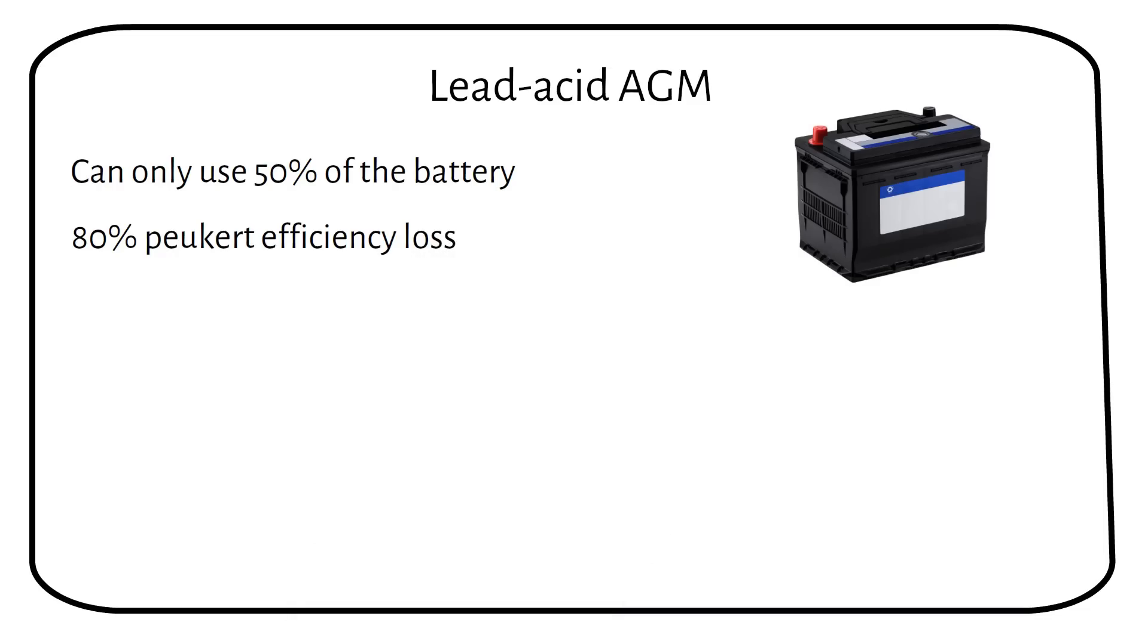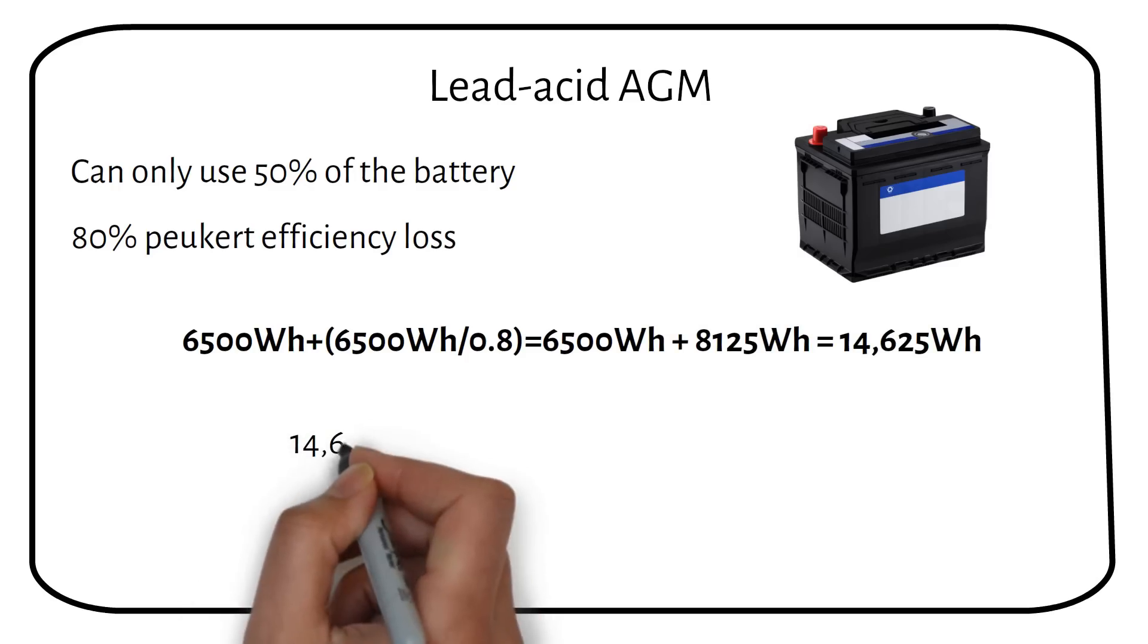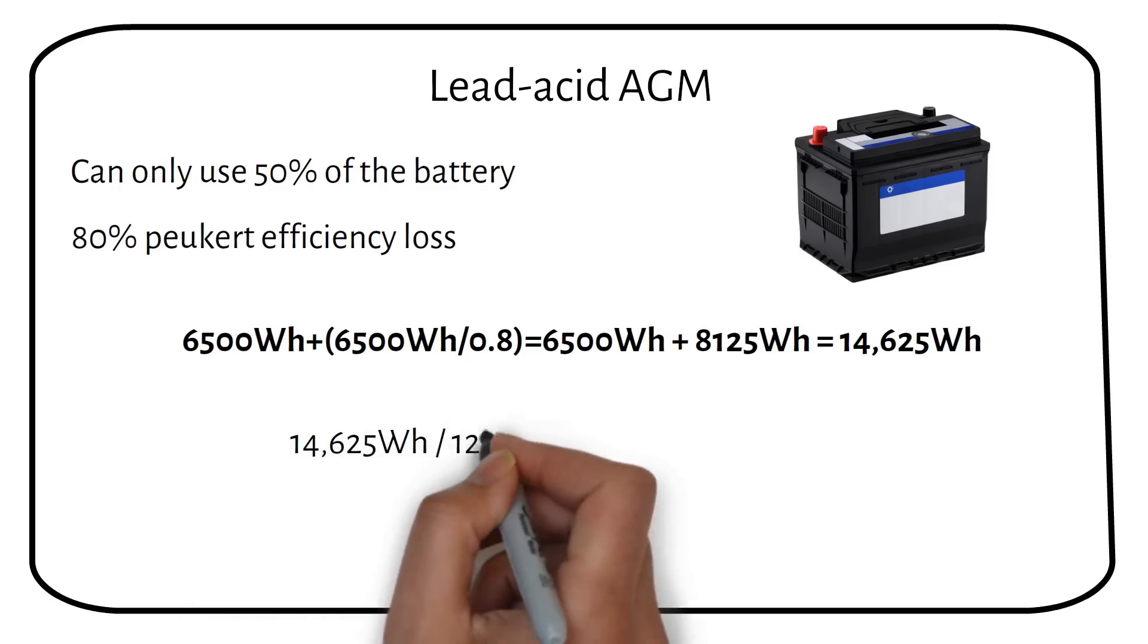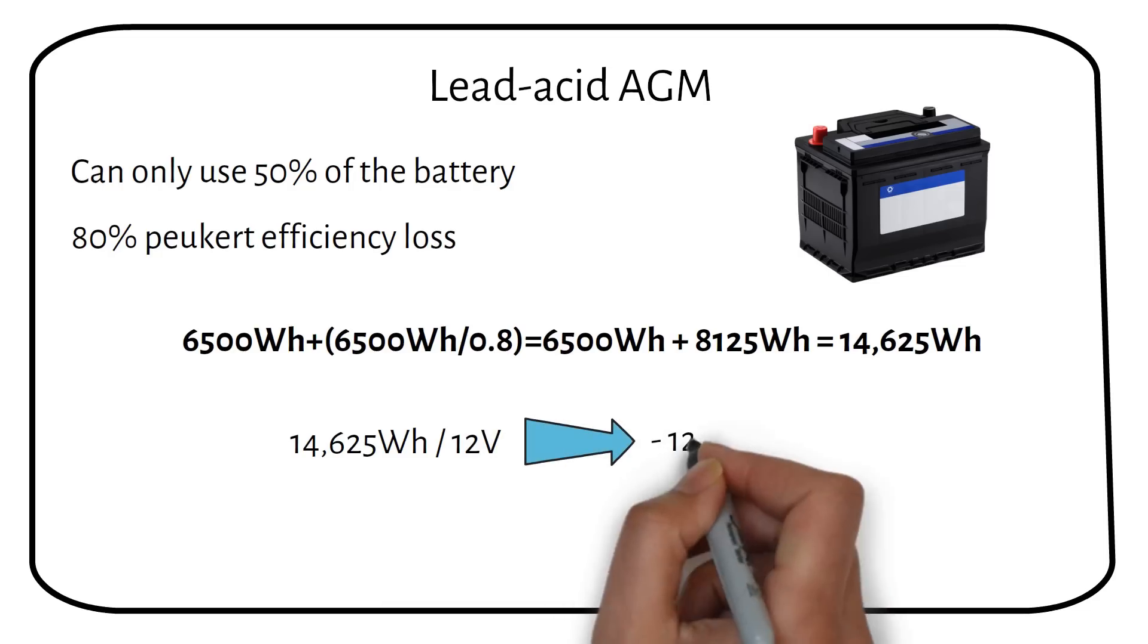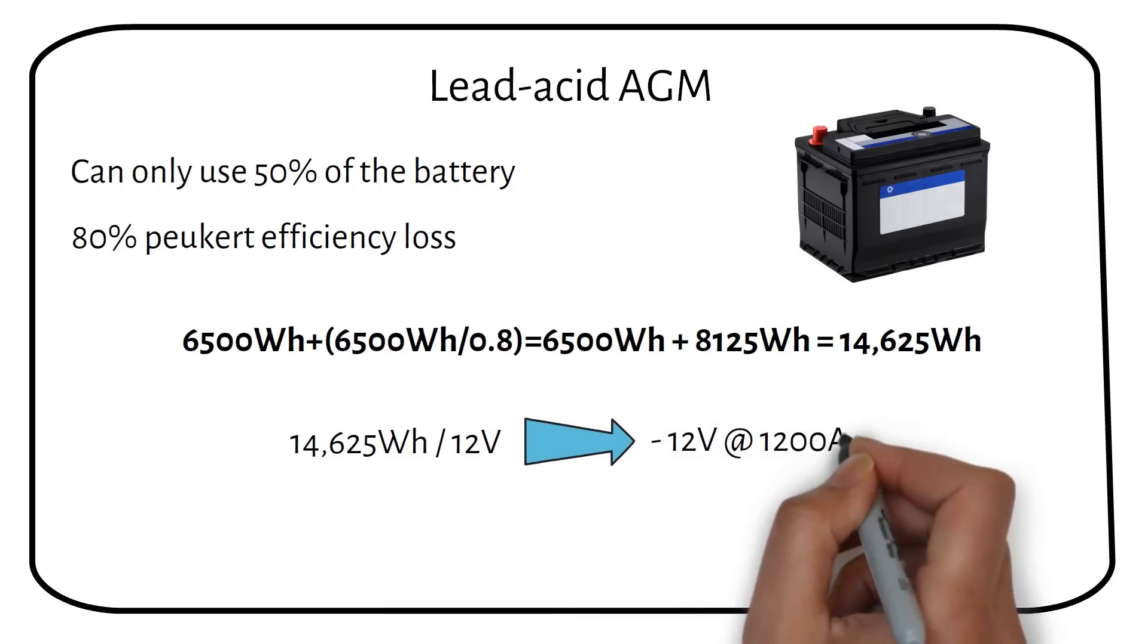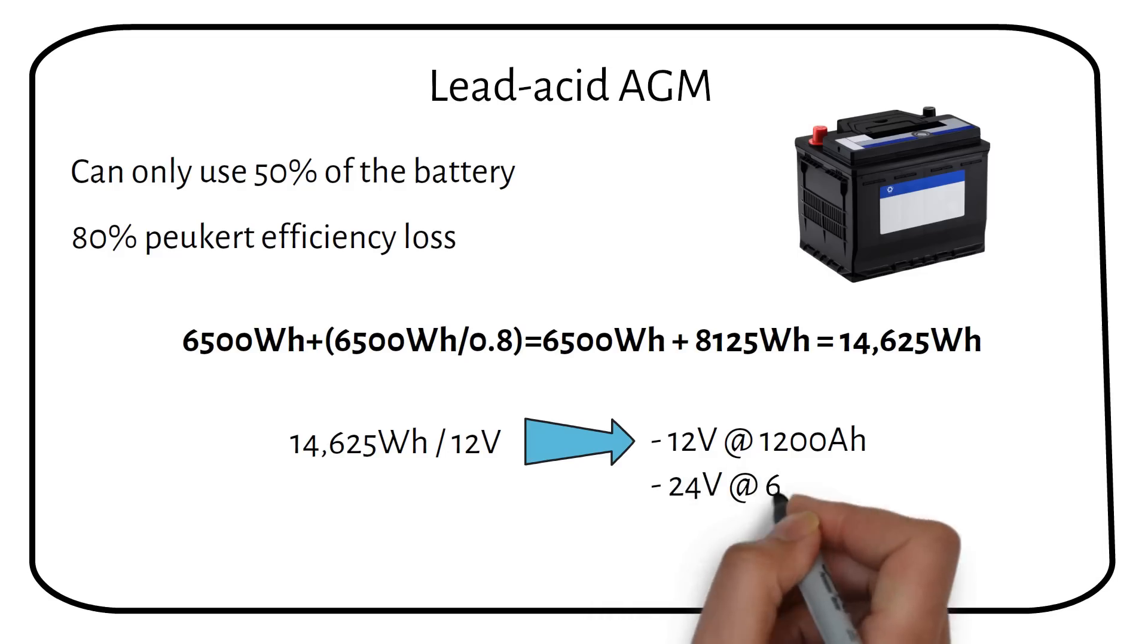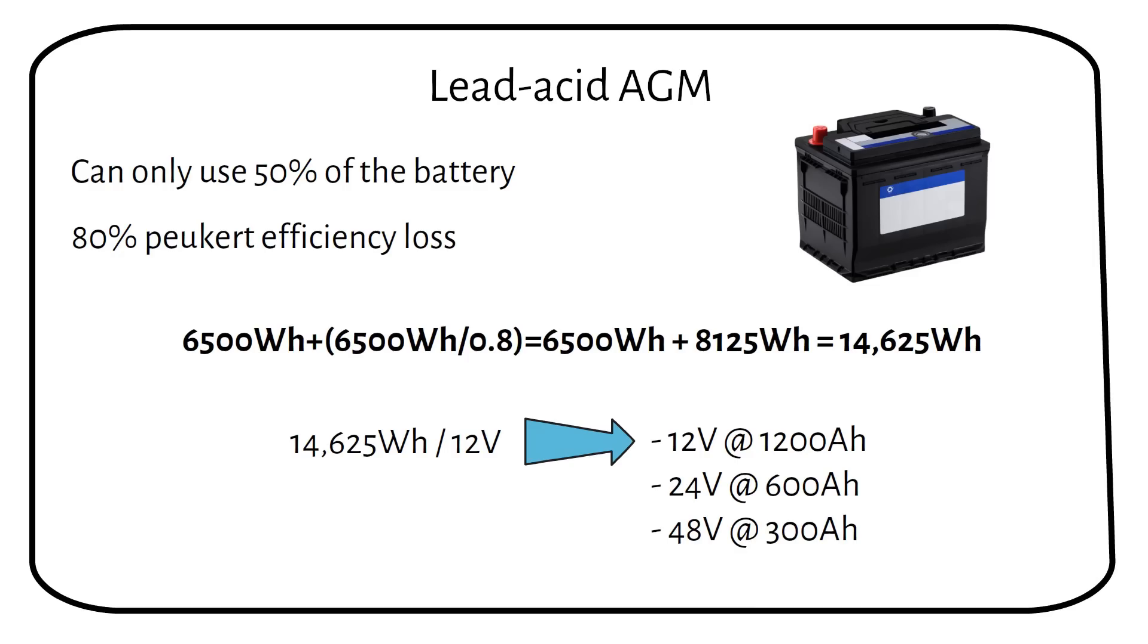This is 80% with a lead-acid AGM battery. We get a total capacity of 14,625 watt hours. Now if the battery is 12 volts, we would need a 1200 amp hour battery. And for a 24 volt battery, this becomes 600 amp hours. And a 48 volt battery, this becomes 300 amp hours.